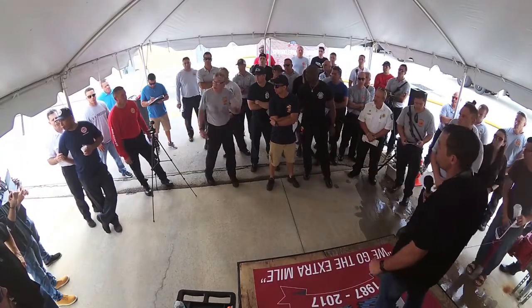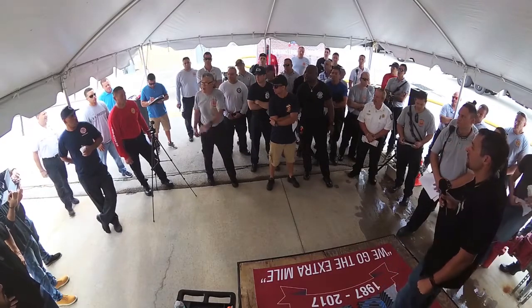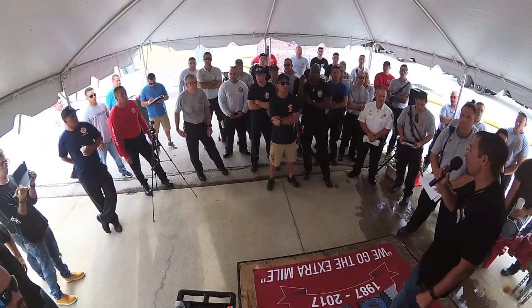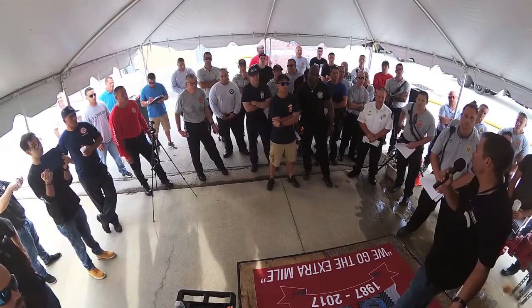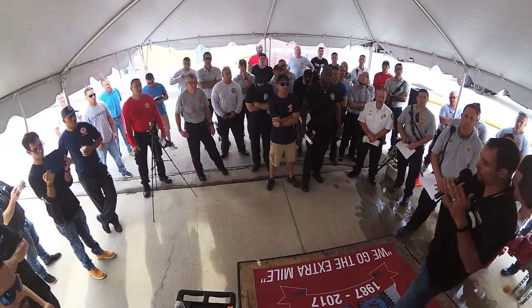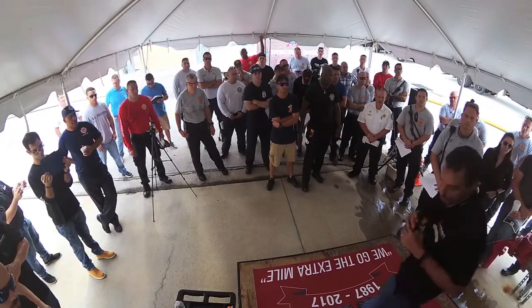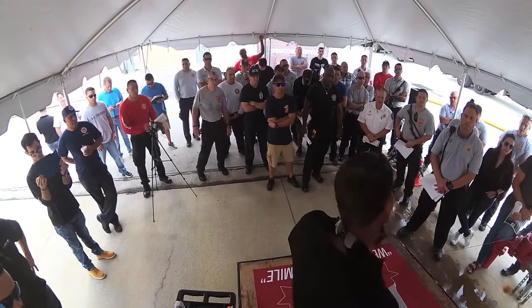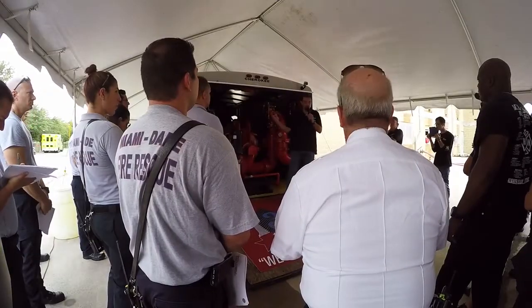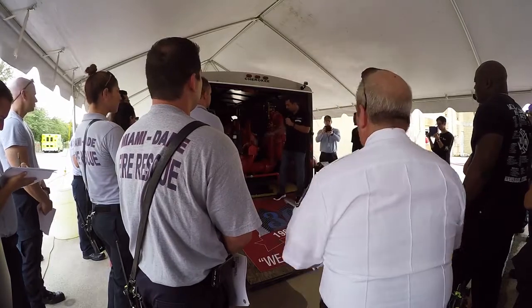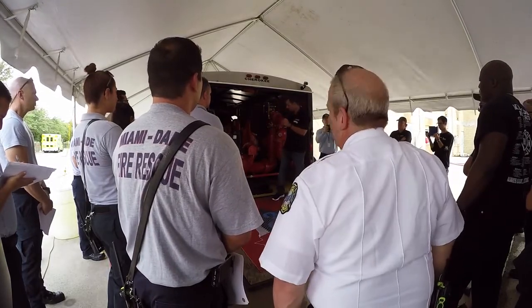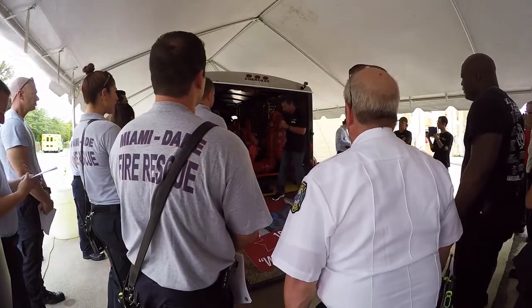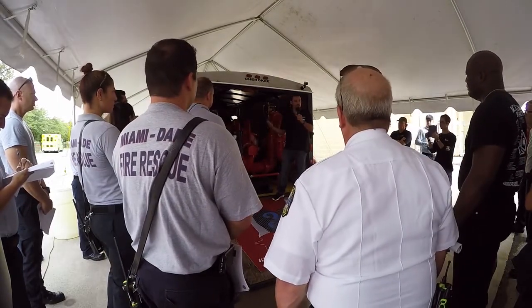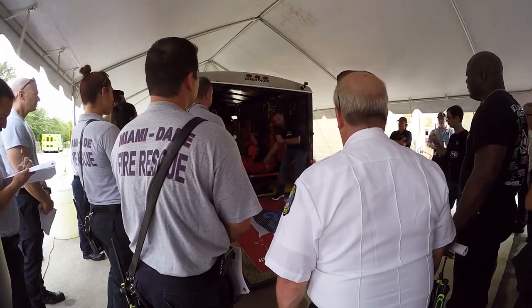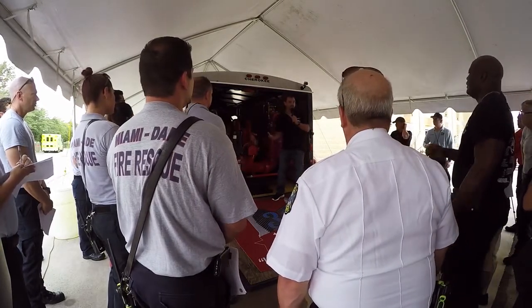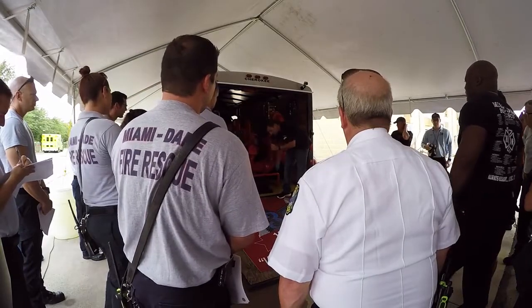Is the pump running? And even more important than that, is it going to continue to run? Right, and if the pump is running, that would mean loss of pressure in the system, okay? That would mean a head's going off, or someone hit a head, or there's an actual fire. So when you get in there, there's some things you should be looking for. Sort of like your pumper truck, when water flows, there has to be some kind of relief in the casing, okay?